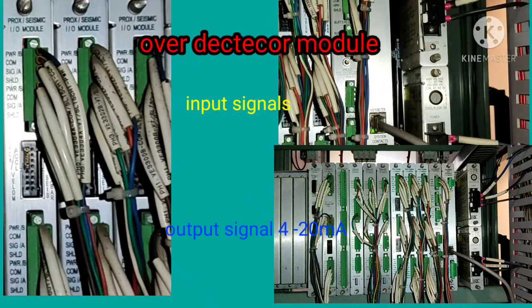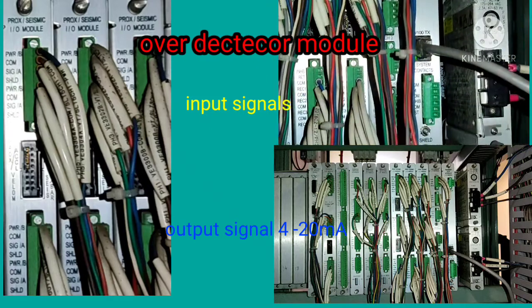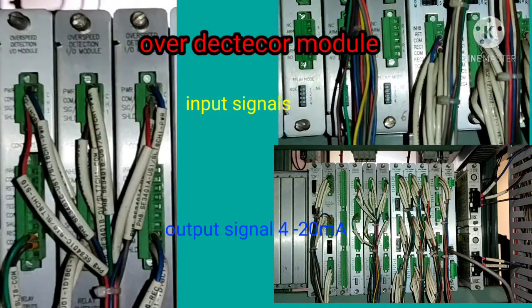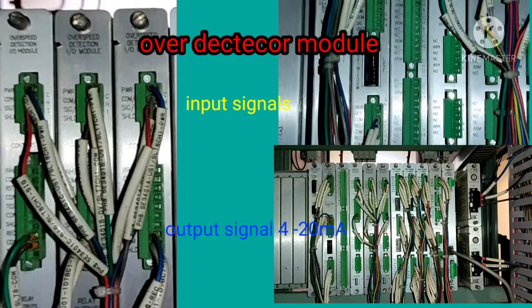The overspeed detection module back panel shows the signal input terminals in the upper portion and the output signal of 4 to 20 milliamps in the lower part, which goes to industrial instrumentation systems.